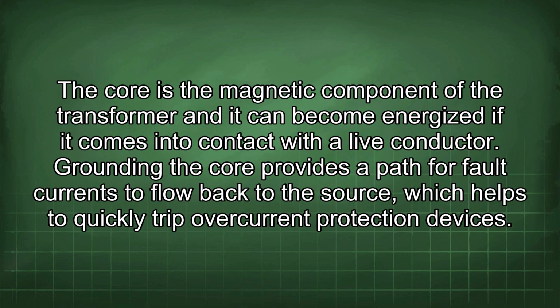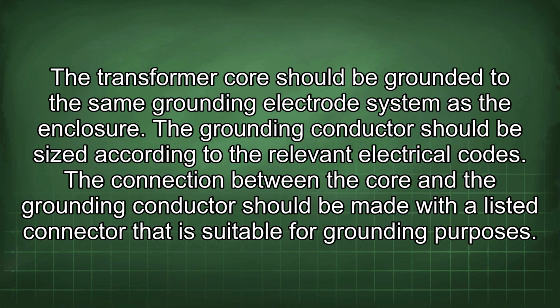The core is the magnetic component of the transformer, and it can become energized if it comes into contact with a live conductor. Grounding the core provides a path for fault currents to flow back to the source, which helps to quickly trip overcurrent protection devices. The transformer core should be grounded to the same grounding electrode system as the enclosure. The grounding conductor should be sized according to the relevant electrical codes. The connection between the core and the grounding conductor should be made with a listed connector that is suitable for grounding purposes.